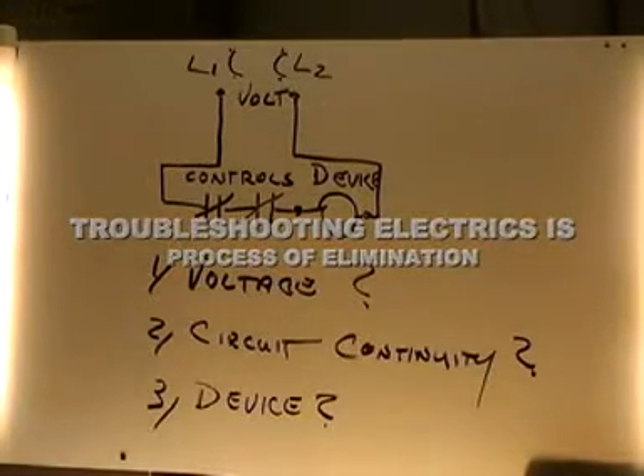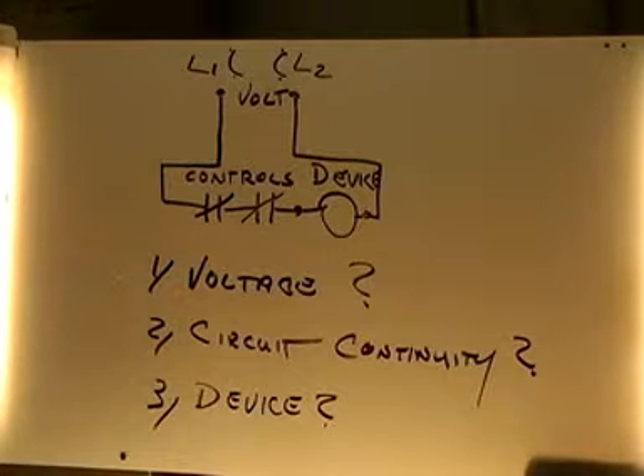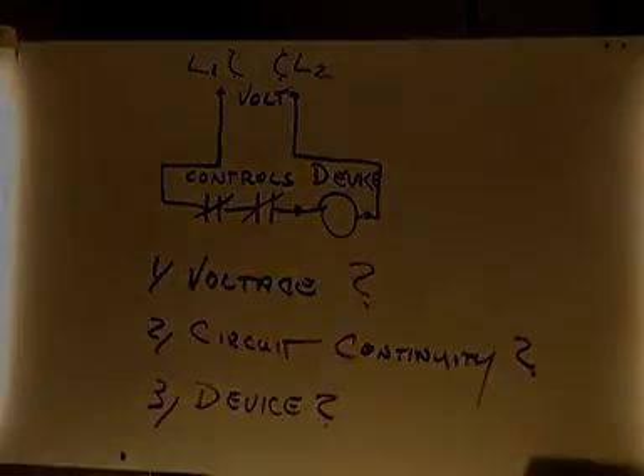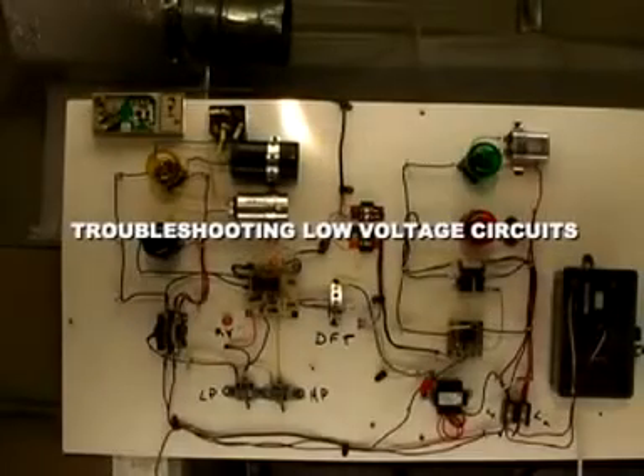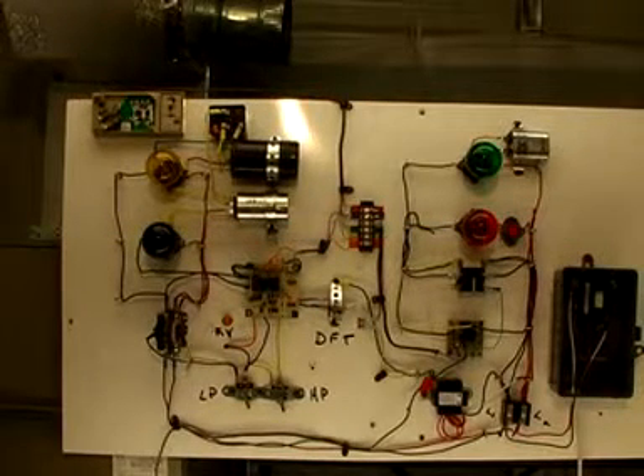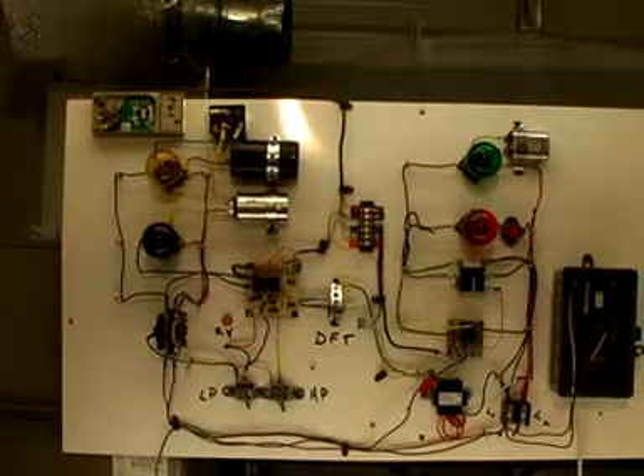If you're getting voltage up here at your source, you say, well, we must have okay voltage. Then, is the circuit closed all the way to the device? How many possible switches could be open or closed? And last but not least, if you've got voltage and the circuit continuity is good, that brings you down to the device. If it's getting voltage and not running, then there's something wrong with the component. Most often it's the low voltage wiring that causes the most problems and headaches, and is usually the most difficult to run down and troubleshoot and locate the problem.